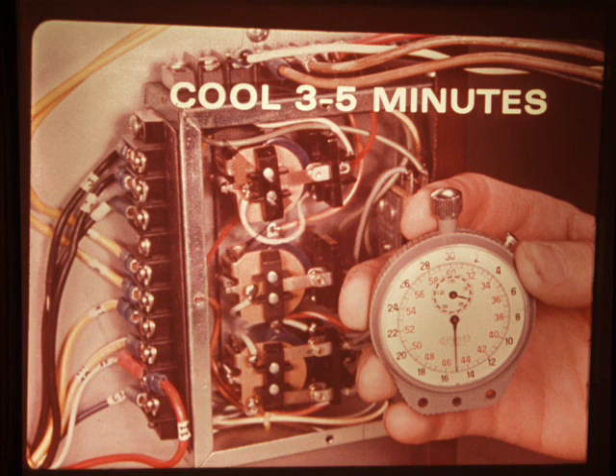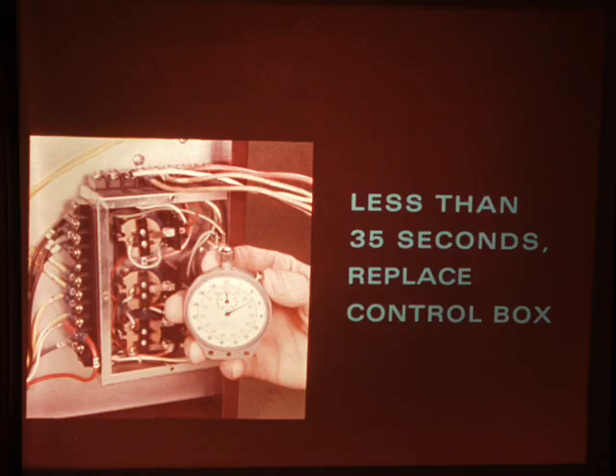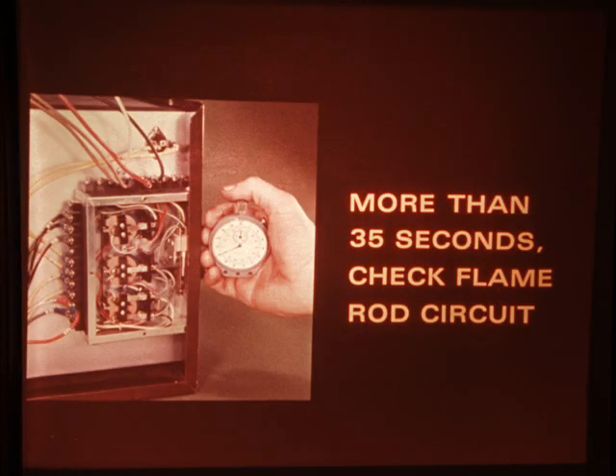When you start your diagnosis, be sure to give the relay time to cool. It may take as long as 3 to 5 minutes. Then, press the reset and turn on the thermostat. Check the time it takes for the reset to pop. If it's less than 35 seconds, the thermal relay is defective and you'll have to replace the control box. If it takes 35 to 45 seconds to shut down the furnace, check the flame rod circuit. So let the reset cool and then push it again.